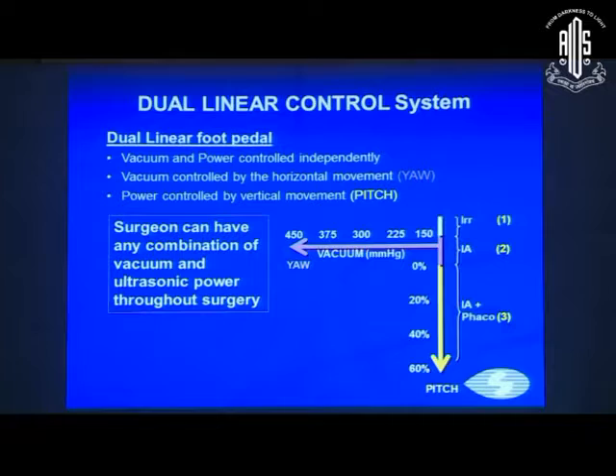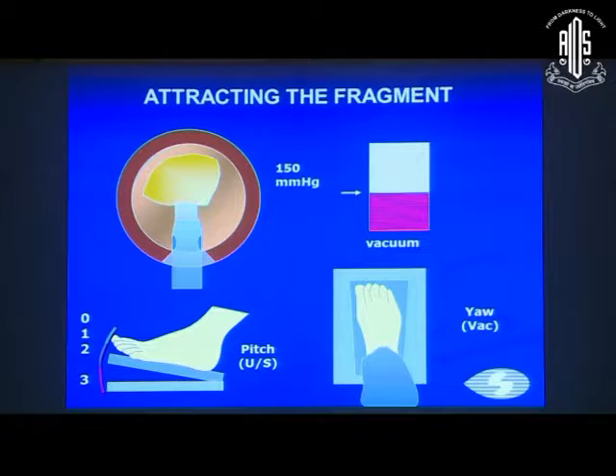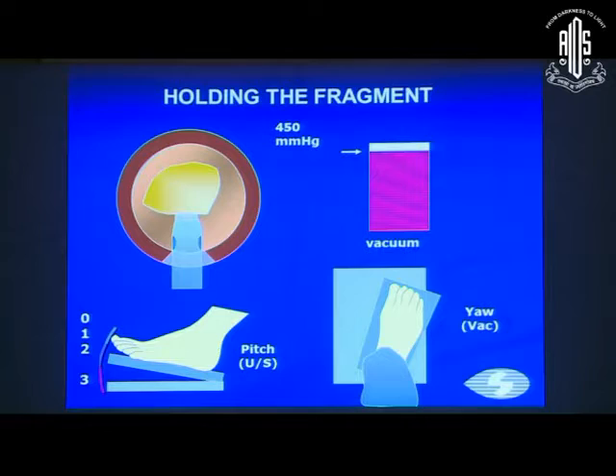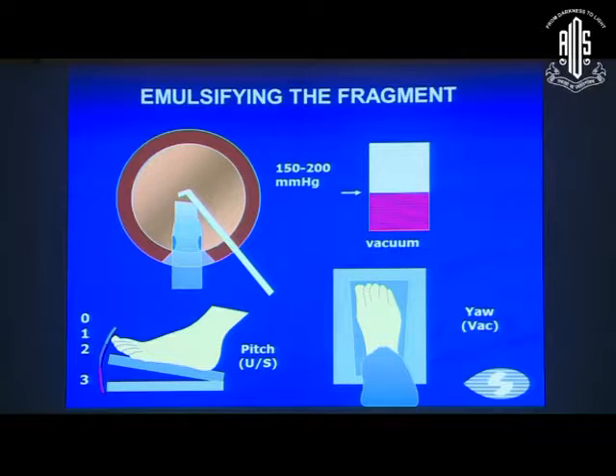The dual linear control system allows vacuum and power to be controlled independently — one in the yaw and the other in the pitch. In this animation, vacuum is in the yaw (horizontal movement) and power is in the pitch (vertical movement). The surgeon can have any combination of vacuum and ultrasonic power throughout surgery: attracting a fragment with lower vacuum of about 150, then impaling it with a burst, then increasing vacuum to 450 in yaw for a good hold, chopping the fragment, and then lowering the vacuum to avoid surge.